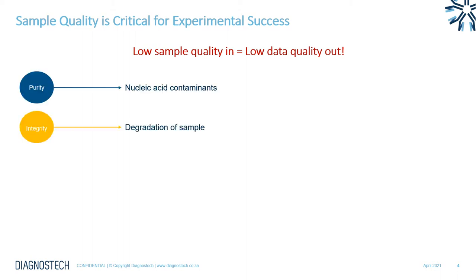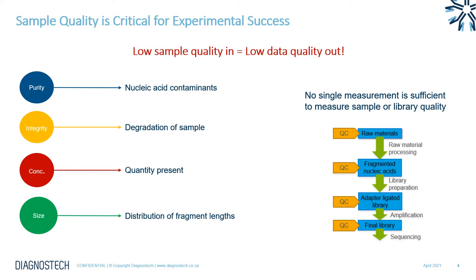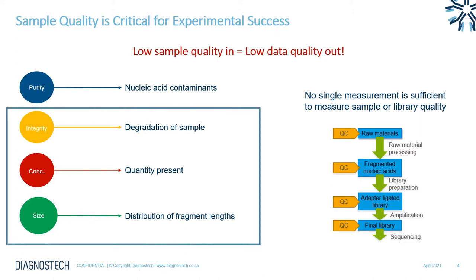There are generally four parameters we want to measure when referring to sample quality: purity, looking at any contaminants in the nucleic acid; integrity, meaning how degraded your sample is (less high molecular weight DNA means more degradation); concentration, meaning what quantity of sample you have available; and size, referring to the distribution of fragment lengths within your sample. A standard NGS workflow representation shows where the different QC steps fall into the workflow. No single measurement is really enough to measure your sample or library quality. The TapeStation is able to measure three of these parameters — integrity, concentration, and size — while purity is generally measured by an instrument such as a NanoDrop.